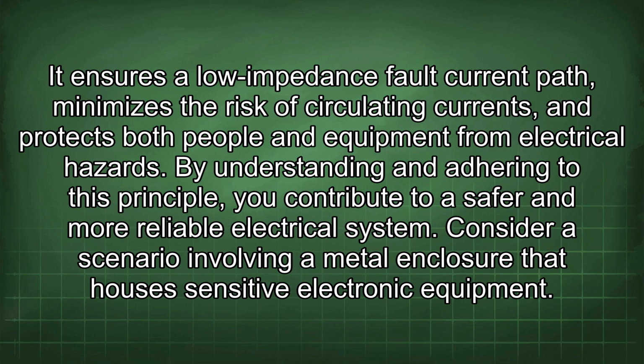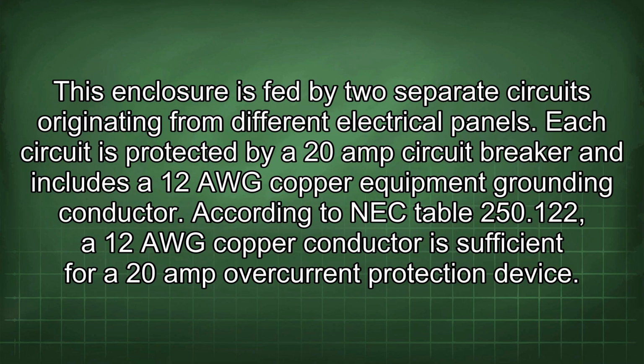Consider a scenario involving a metal enclosure that houses sensitive electronic equipment. This enclosure is fed by two separate circuits originating from different electrical panels. Each circuit is protected by a 20-amp circuit breaker and includes a 12 AWG copper equipment grounding conductor. According to NEC Table 250.122, a 12 AWG copper conductor is sufficient for a 20-amp overcurrent protection device.